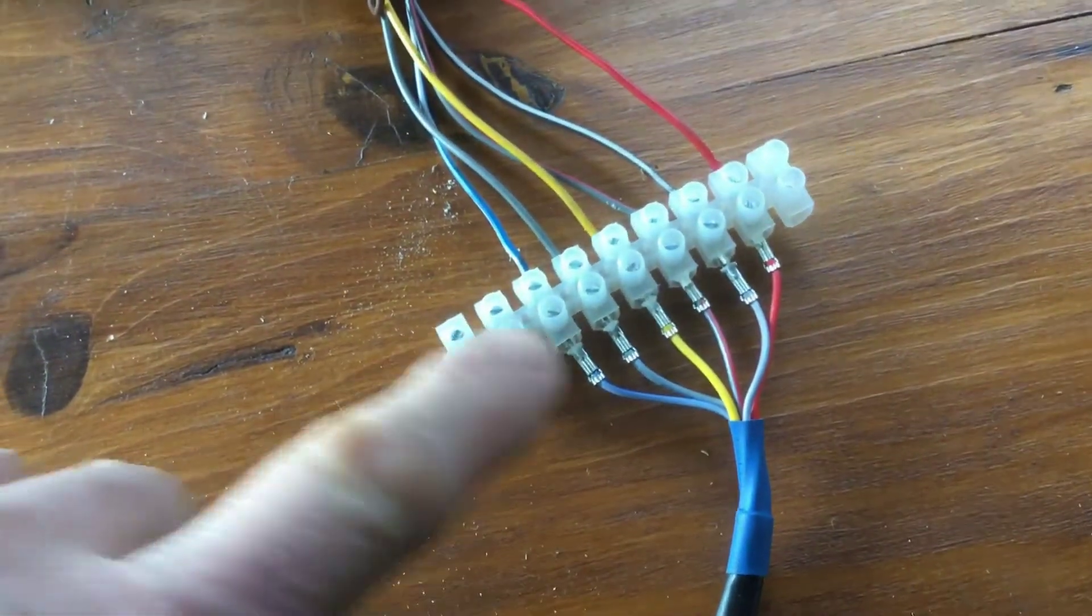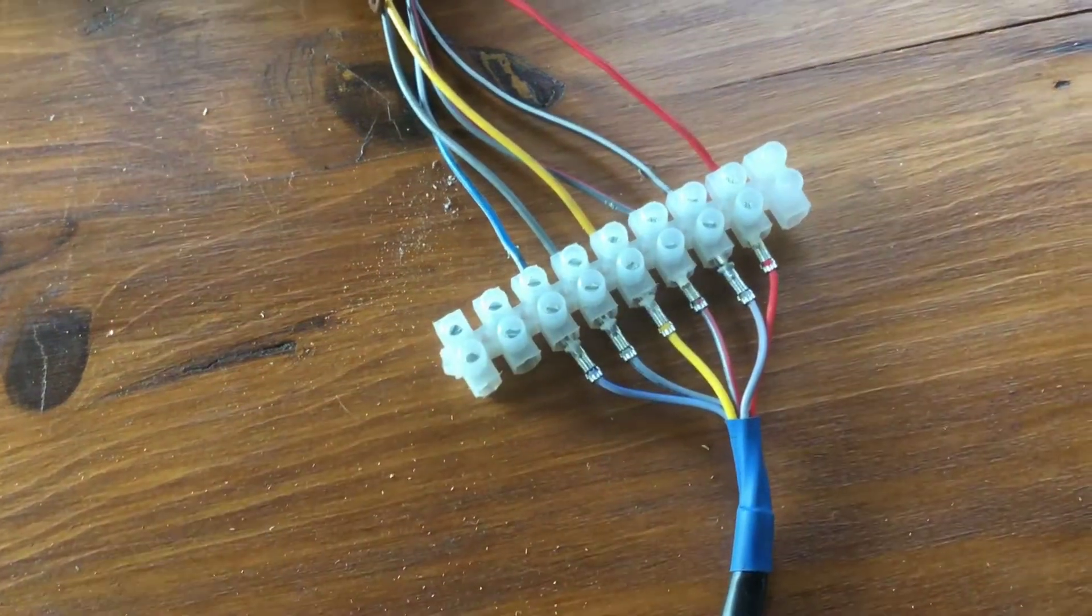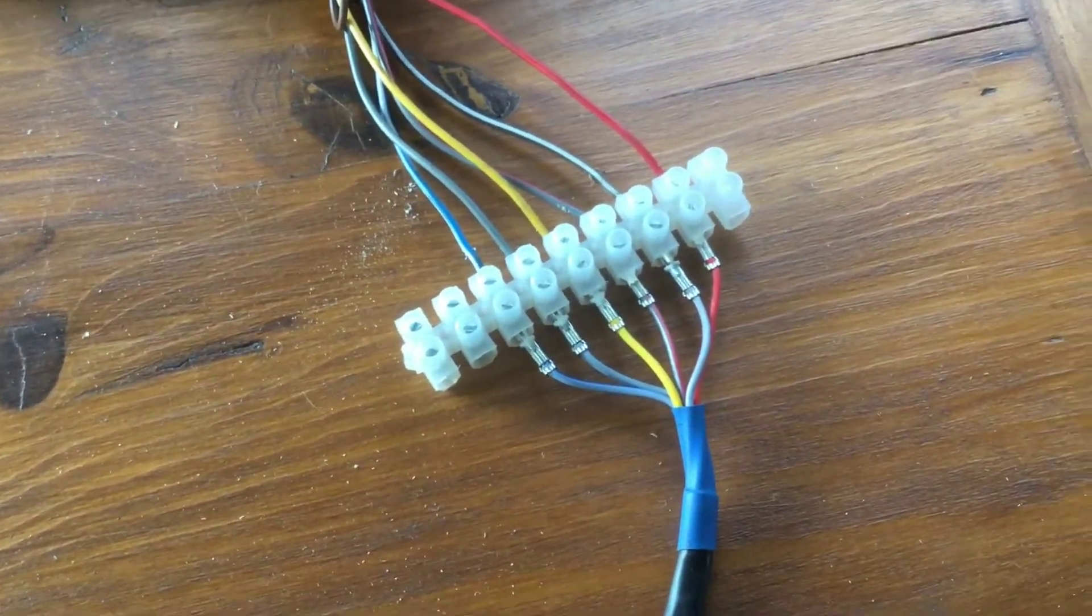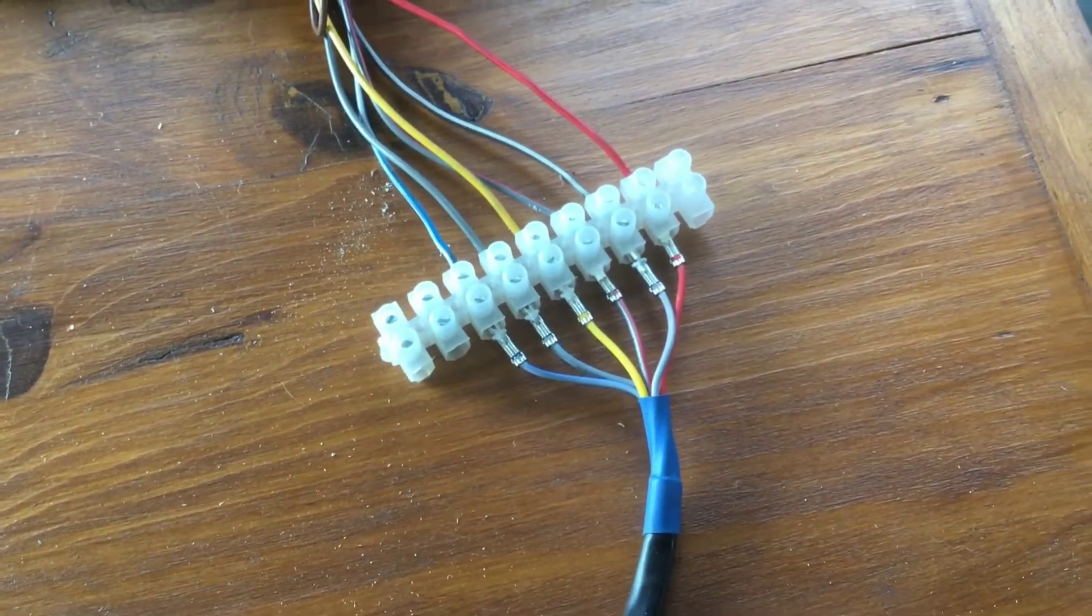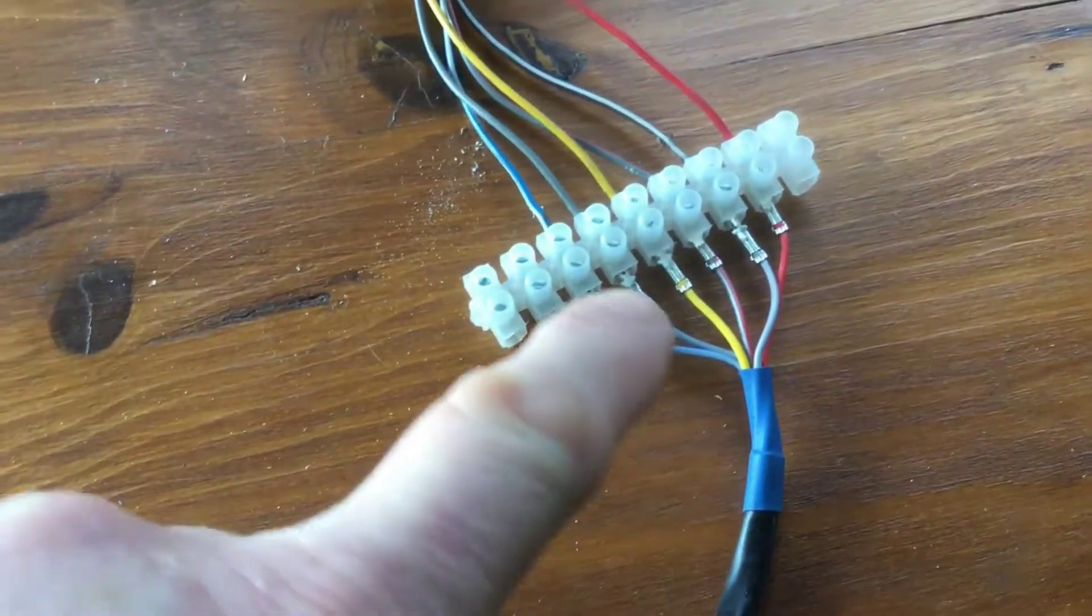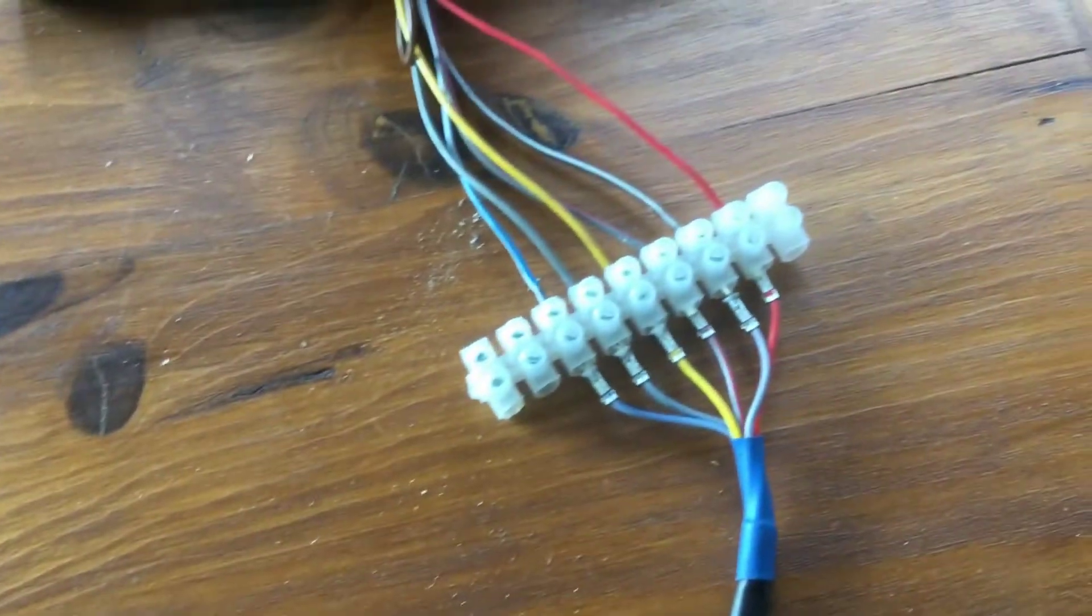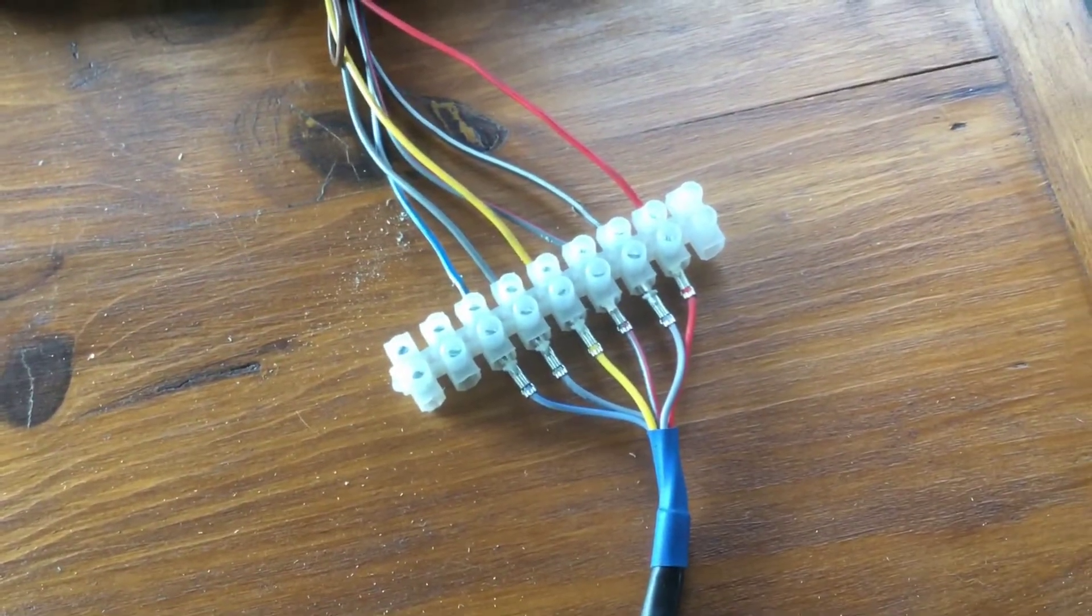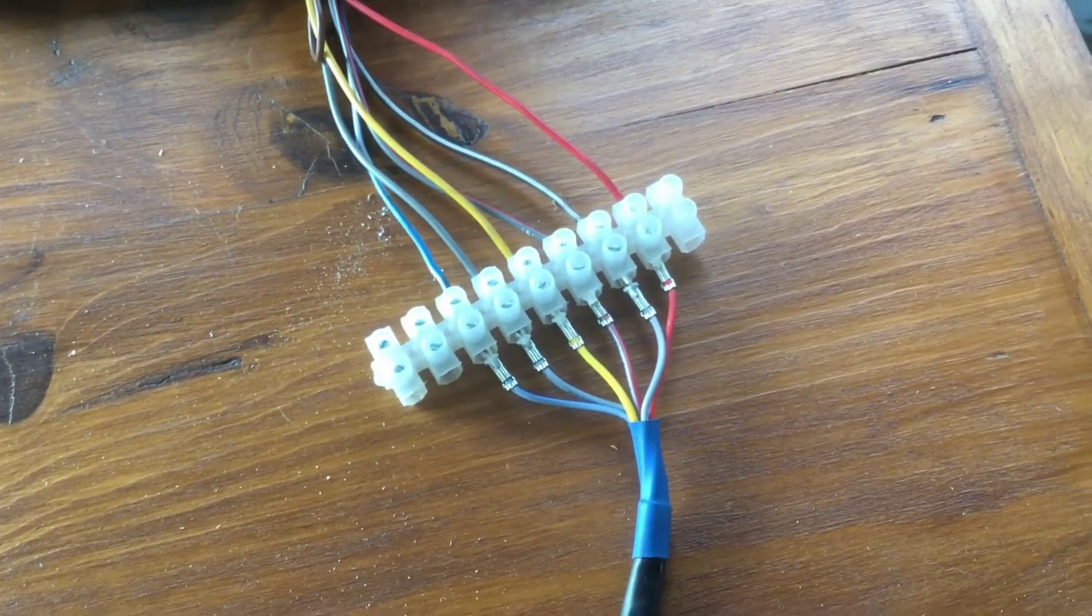The other one, the grey one, bypasses the temperature sensor on the side of the heater that measures the temperature of the cooling air. And by having two sensors inside the controller you get a much better process of modulating the blower fan.